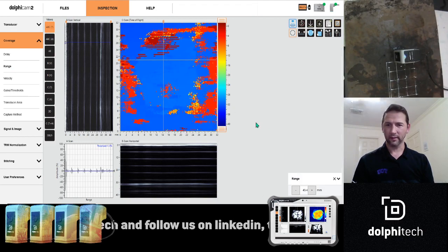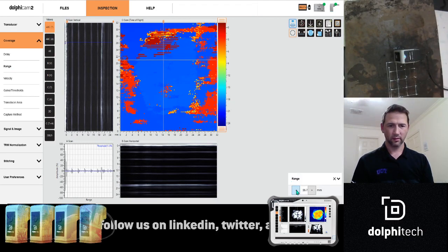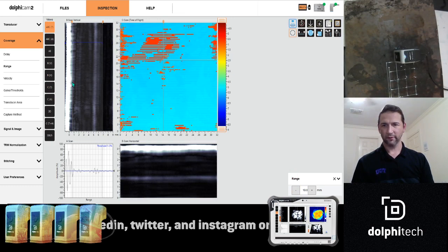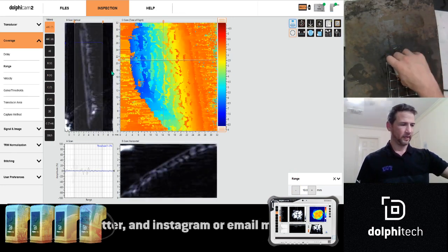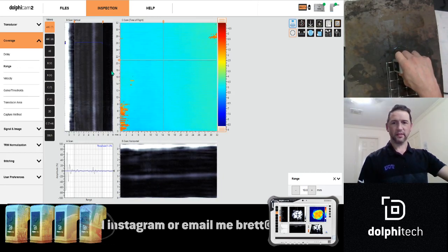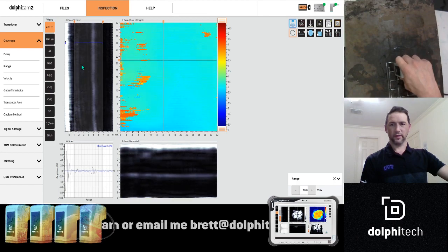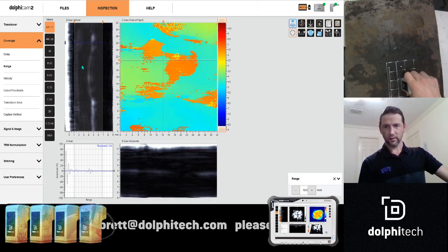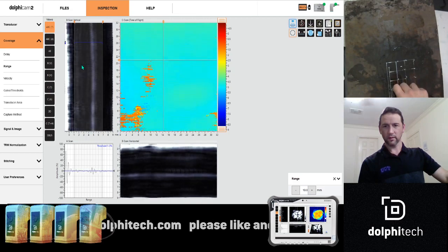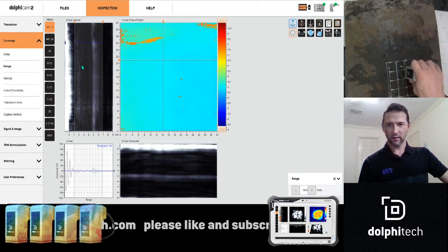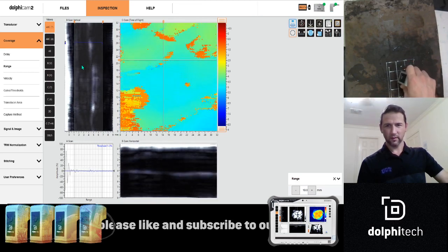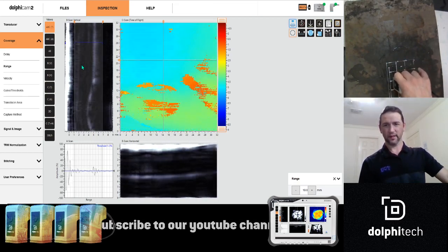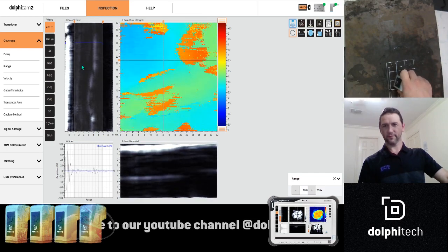Stainless steel, and let's go to range. There we go. Here's my front wall echo. Here's my back wall. Let's clean it up. This one does have some corrosion in it. So as you can see, if you're watching your B scan right here, you will see some variation start to occur. Here's one. That's a nice one right there. So, perfect.